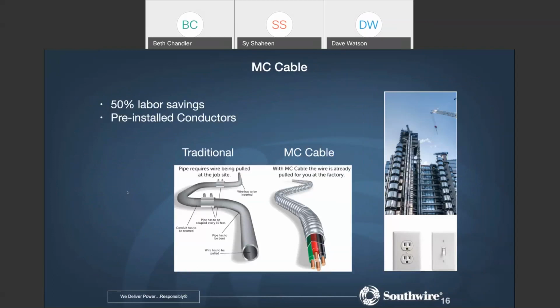Just a couple of slides on MC cable. Again, the more detailed presentation will be coming next week. But MC cable does get utilized in data center applications. This is where you have pre-installed conductors, meaning that you have conductors that are factory installed inside of a flexible sheath or armor. So this is going to be like a flexible metal conduit, but when you receive the product, it's all as one cable. And this is, I think, especially popular for the smaller size conductors for the branch circuits in data centers. So they provide quite a bit of labor savings compared to the pipe and wire type of installation where you're pulling individual conductors through a piece of conduit. Next.